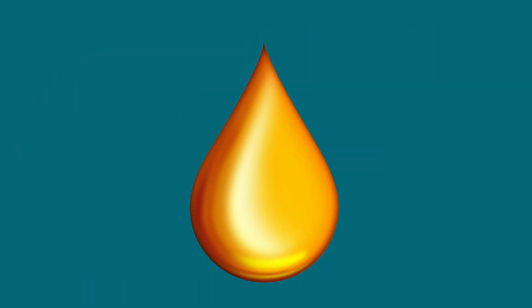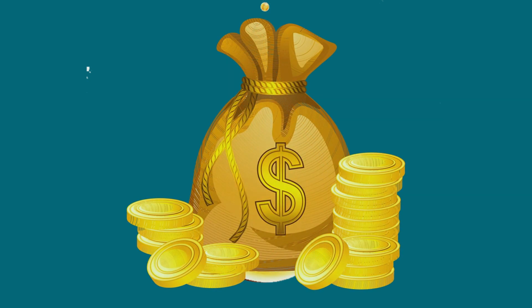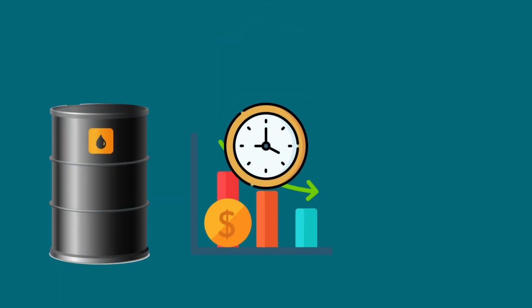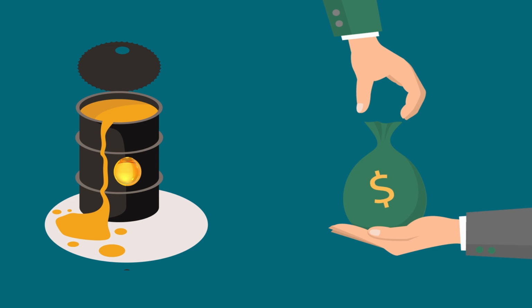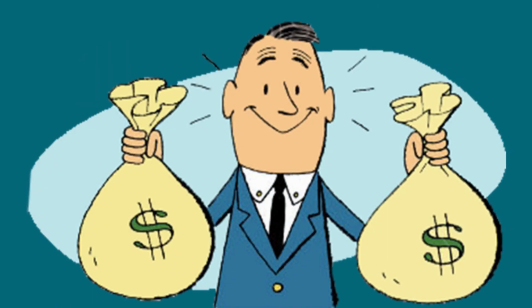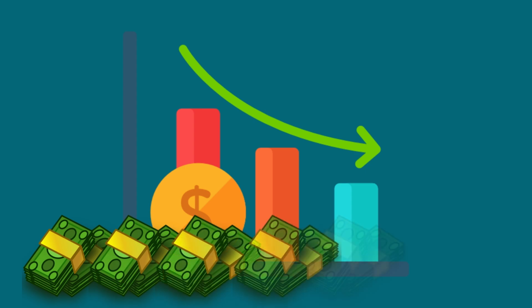One of the options to prevent this kind of problems is to change Fyrquel liquid to a new one. However, it entails high financial costs, including the cost of purchasing a new fluid, the losses associated with the downtime of power generating equipment, which may last up to 2 weeks or even longer, the cost of remuneration for workers changing the fluid, payment for disposal of waste fluid, purchase and disposal of flushing fluid. In a best-case scenario, the cost of changing the fire-resistant fluids will be measured in tens of thousands of dollars. And in the event of power-generating equipment failure due to contamination of fire-resistant fluid, losses may reach millions of dollars.